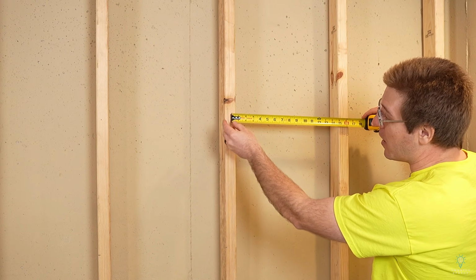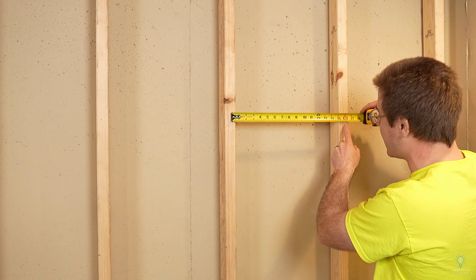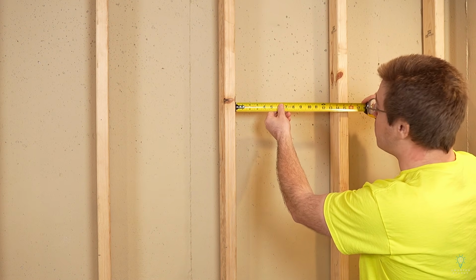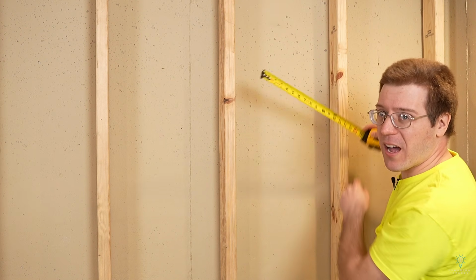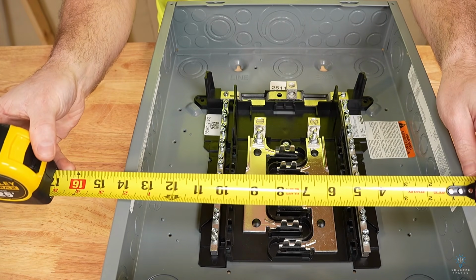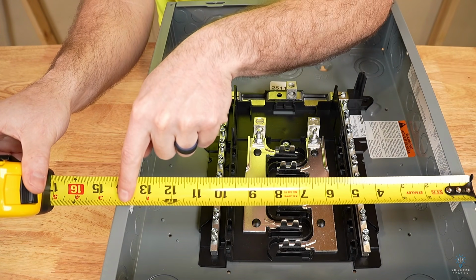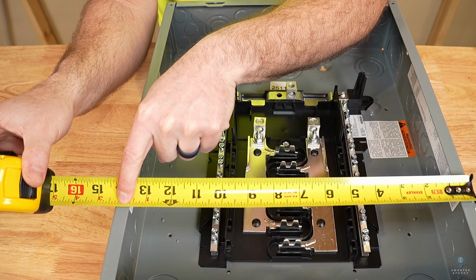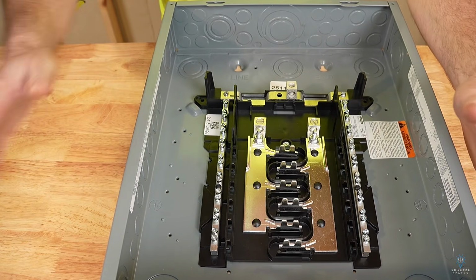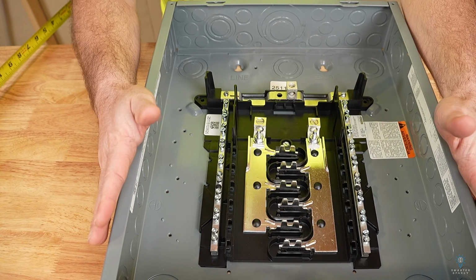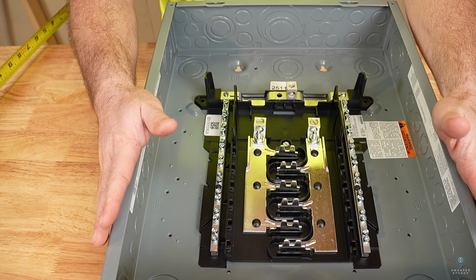Now these studs are installed 16 inches on center. What that means is our stud from the center of this stud to the center of this stud is exactly 16 inches. So that means between them, we have approximately 14½ inches. And if we come over and measure our electrical panel, we're gonna notice the panel is exactly 14½ inches wide. So these panels are actually made for 16-inch on-center stud pockets.